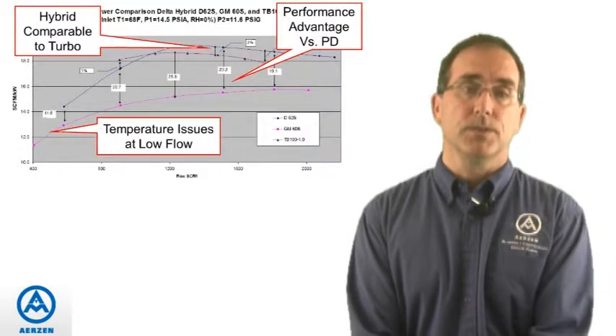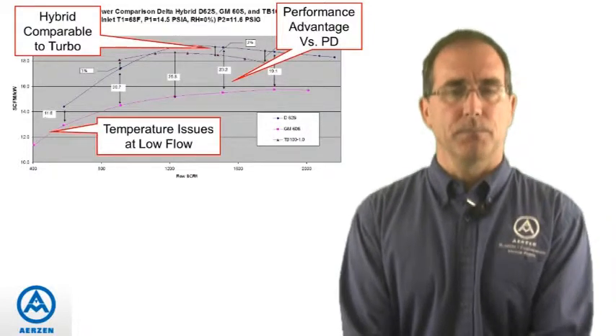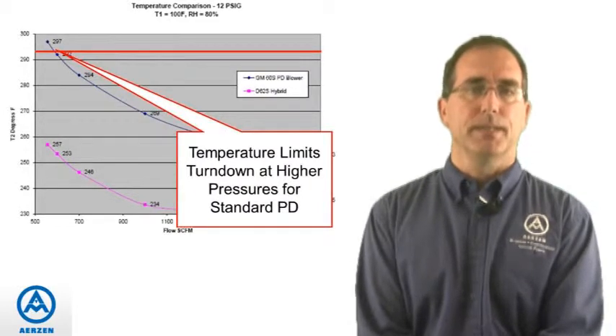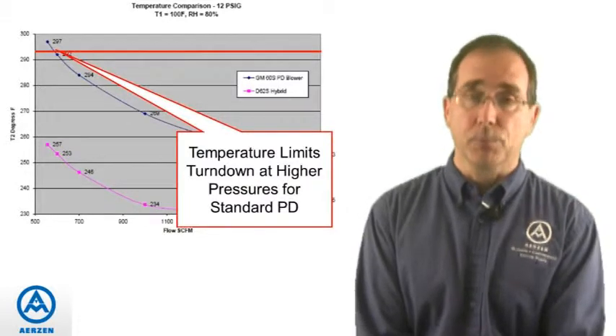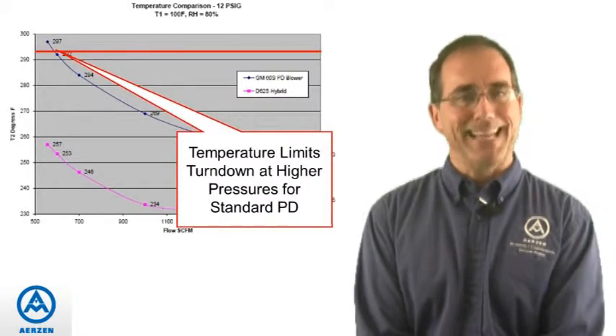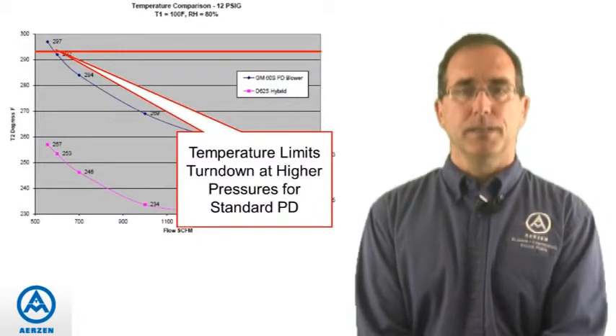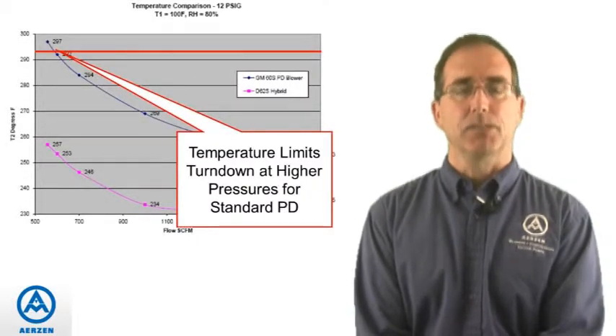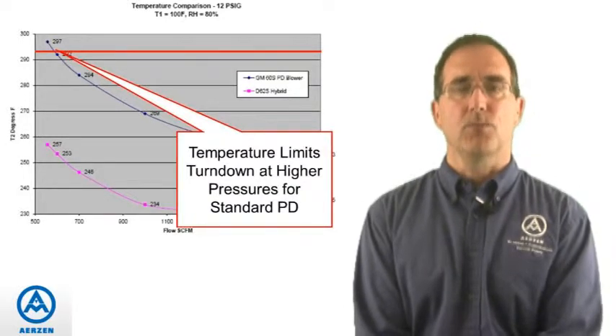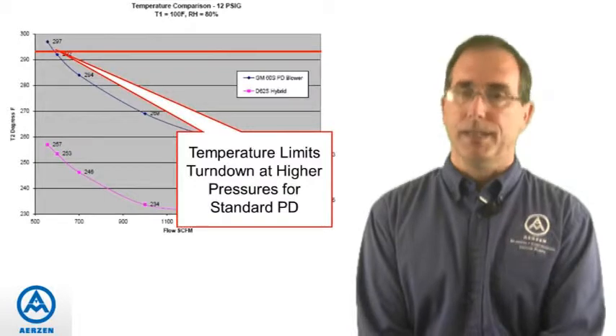The hybrid is actually comparable in performance to the turbo. Even though the standard PD blower has that turndown range, you can run into temperature issues at low flow. Here's a diagram that shows the discharge temperature of a standard PD blower and our hybrid at a given set of high-pressure conditions. The red line on this diagram is the maximum allowable temperature for that blower, beyond which you start to damage it. As the flow slows down, the discharge temperature actually increases. For the standard PD blower, it hits that maximum temperature before reaching the rotational limit, which limits your turndown — whereas the hybrid, because it's running more efficiently, never even gets close to that.